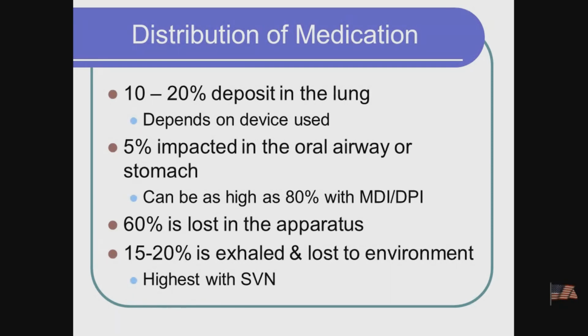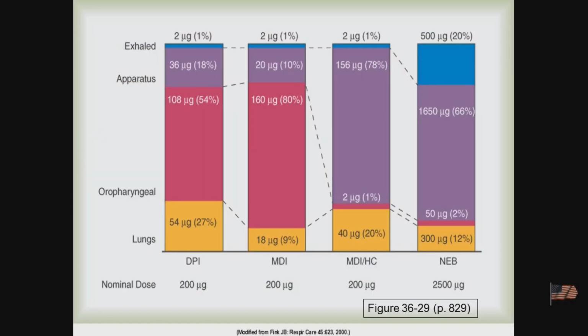Okay. A lot of it's lost in the apparatus: the tubing, the mask, the mouthpiece, the nebulizer itself. And because a nebulizer typically generates aerosol continuously, some of it is generated during exhalation, which is a total waste. So it's a loss to the environment.